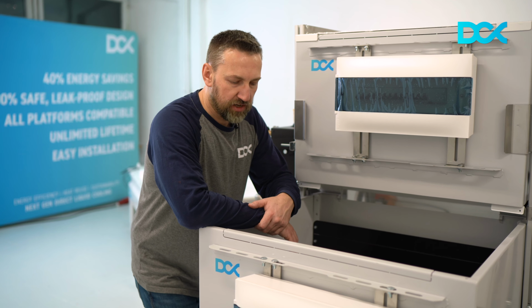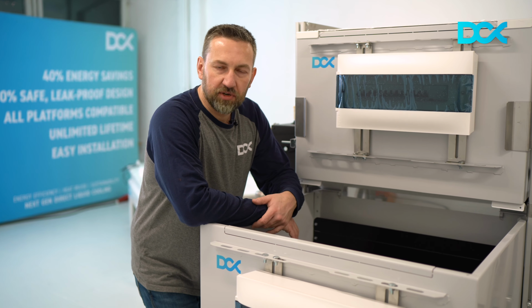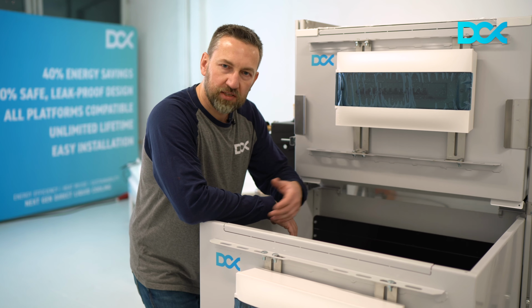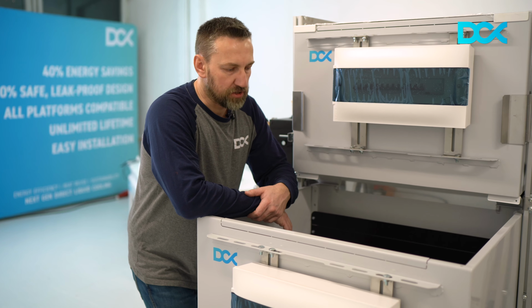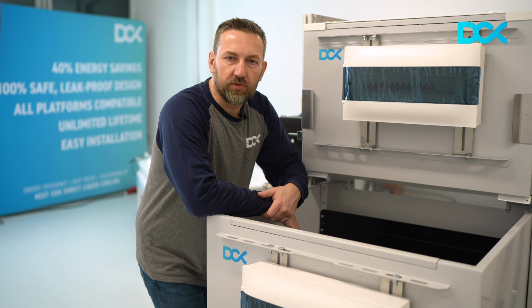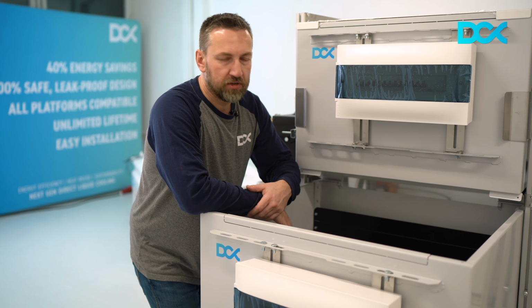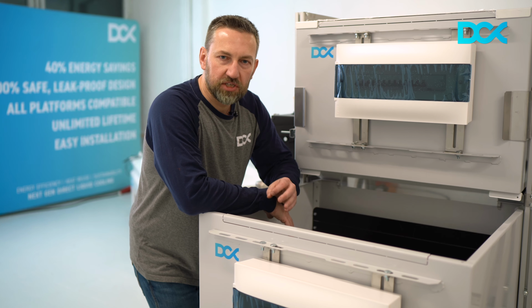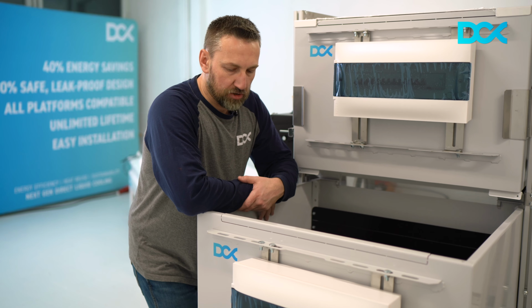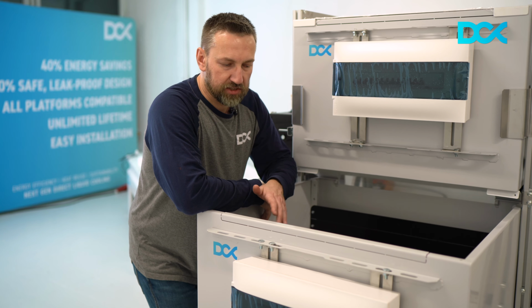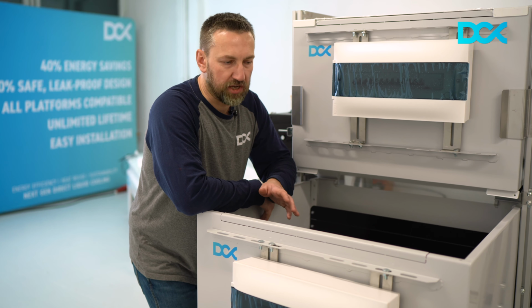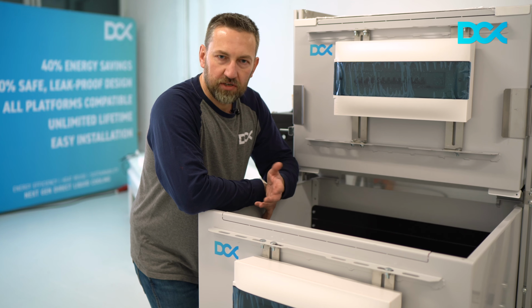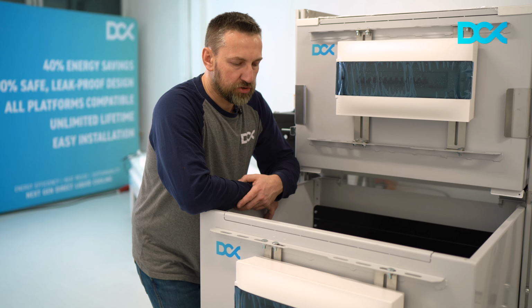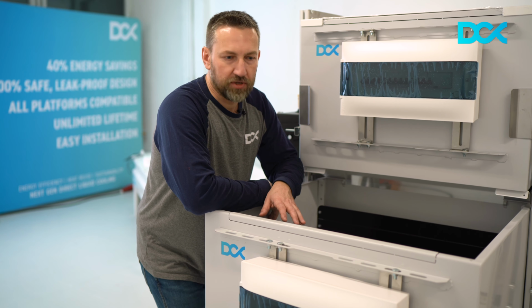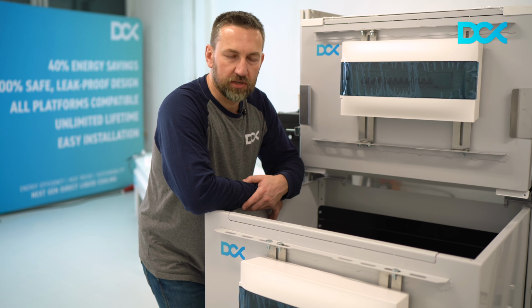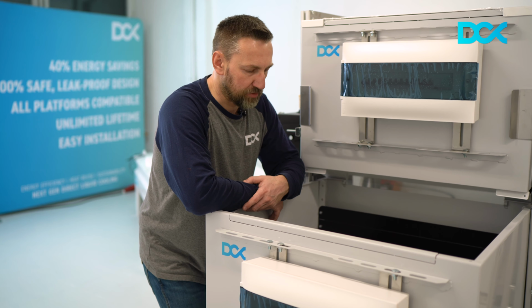So we have a great delta T, a great temperature difference between the inlet and outlet. It's 20 degrees Celsius. So if we are coming into the enclosure with 40 degrees Celsius, we are going out with 60 or over 60 degrees, and this is what we aim for. So that enclosure will also be hot. Take that into account when you locate it somewhere in the garage or in the cellar or anywhere. But make sure that there is also proper ventilation around, because it will be just hot, especially during the hot season, especially during the summer.